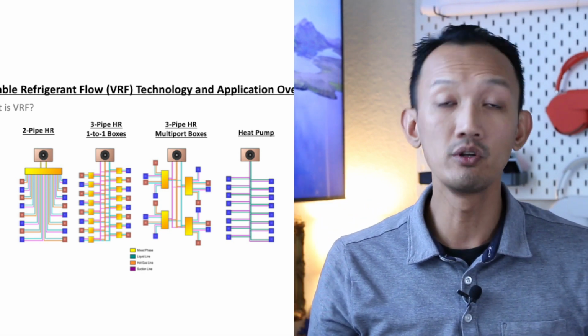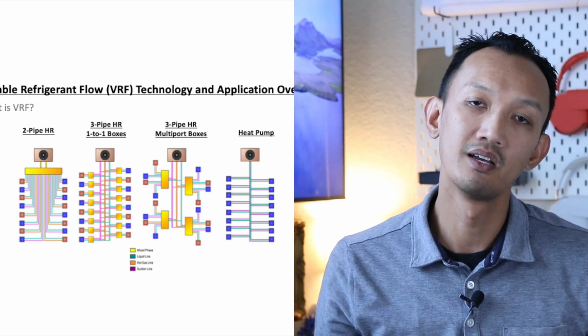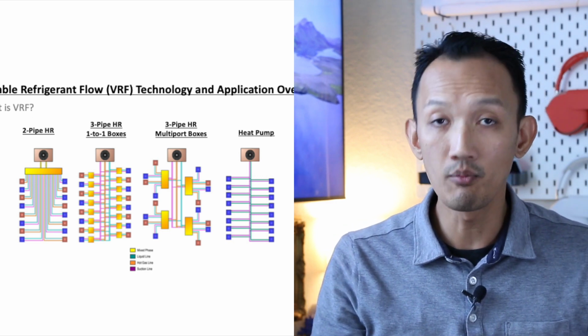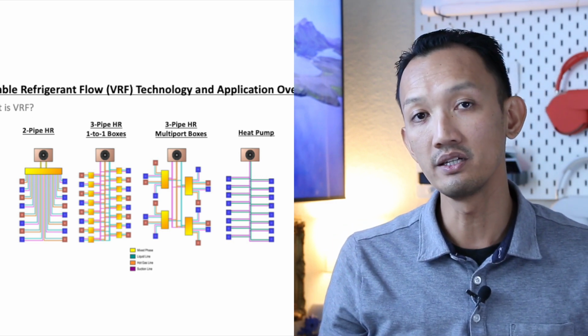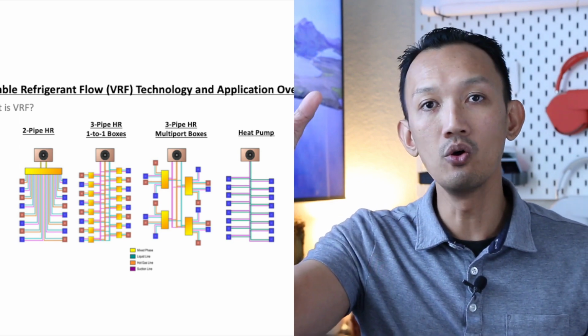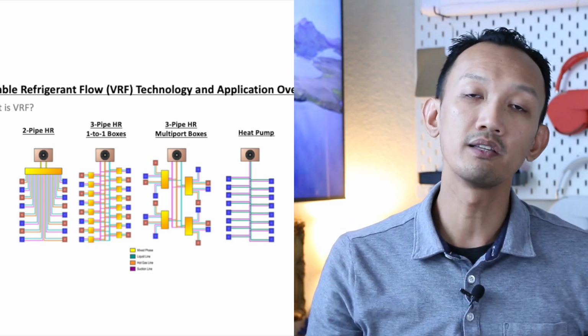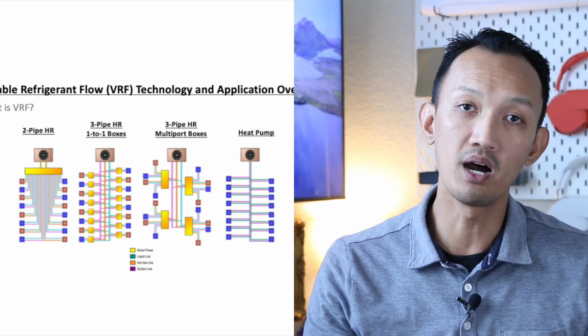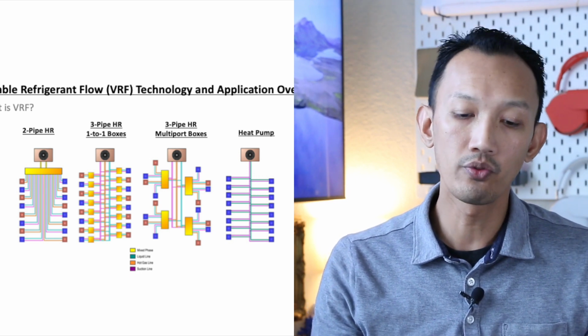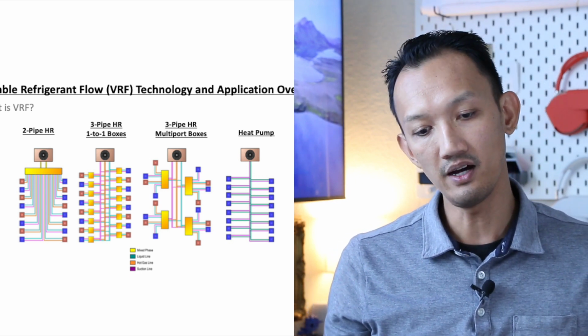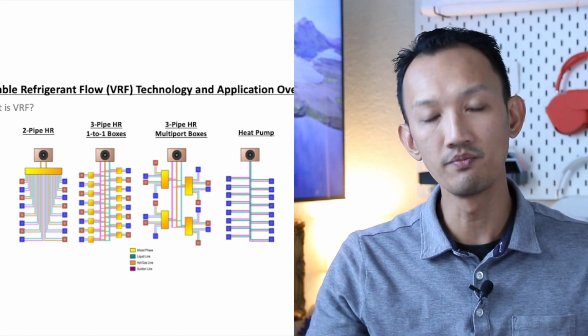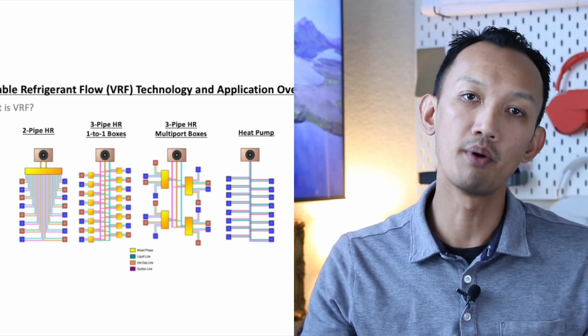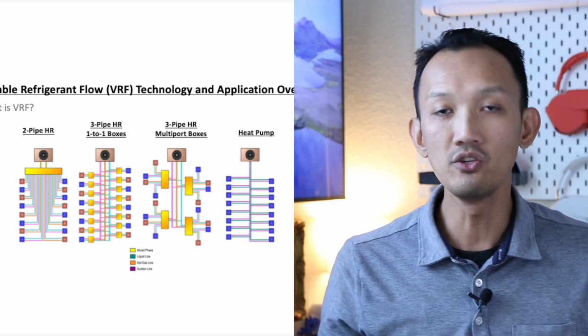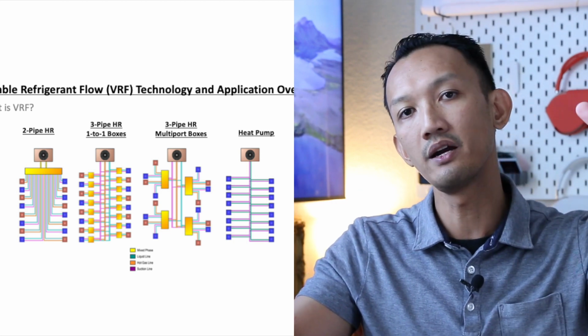If you look at the three-pipe heat recovery with the one-to-one boxes, it's less piping, but you have a lot more labor since you're installing each fan coil with its own single-port box. If you look at the three-pipe heat recovery with multi-port boxes, it's a little bit of best of both worlds.